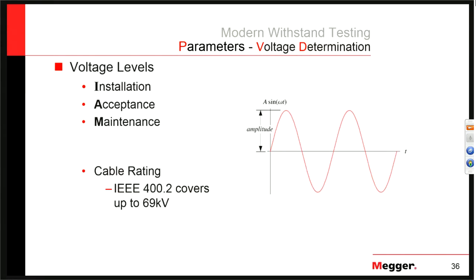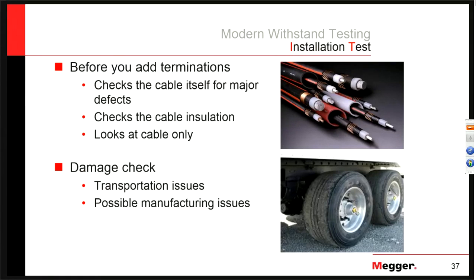Frequency and waveform are decided at the time of purchasing the VLF test set. When actually at the cable, we have to decide voltage level and test duration. IEEE has three voltage levels depending on where the cable is in its life: the installation test — basically a delivery check that can be done with cables still on the reel — just looking for damage during shipping. More than once, I've heard of truck drivers stapling the bill of lading directly to the cable, leaving holes that will cause trouble later — a VLF installation test is very likely to detect something like that.